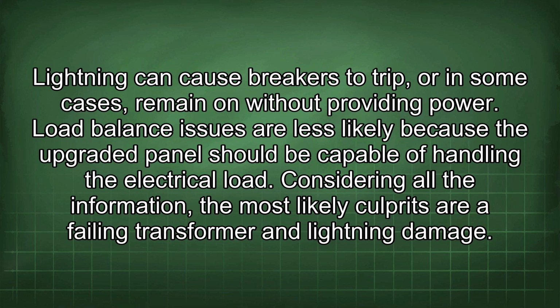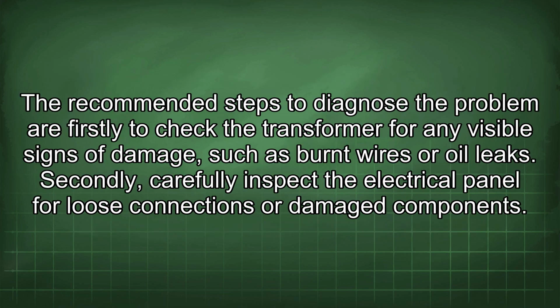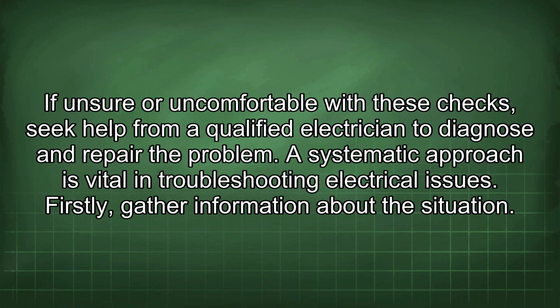Considering all the information, the most likely culprits are a failing transformer and lightning damage. The recommended steps to diagnose the problem are firstly to check the transformer for any visible signs of damage, such as burnt wires or oil leaks. Secondly, carefully inspect the electrical panel for loose connections or damaged components. If unsure or uncomfortable with these checks, seek help from a qualified electrician to diagnose and repair the problem.